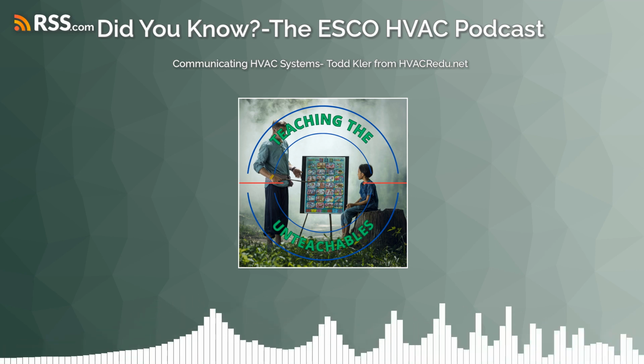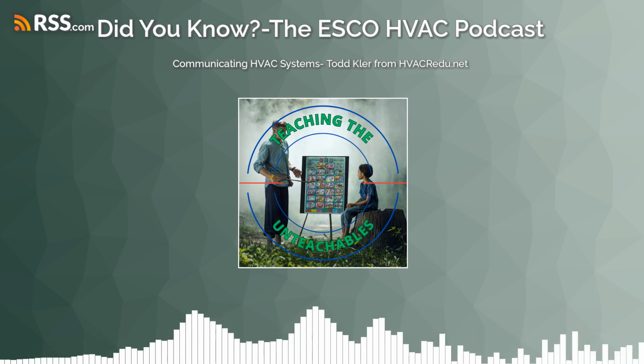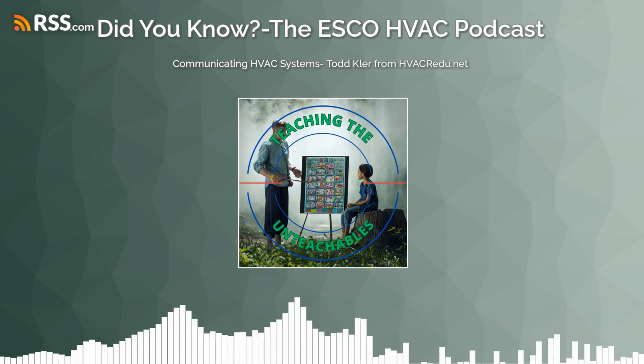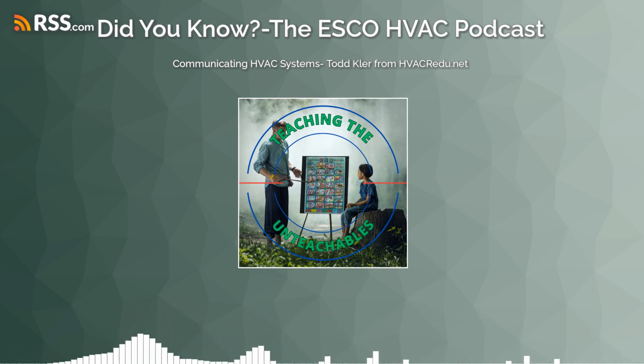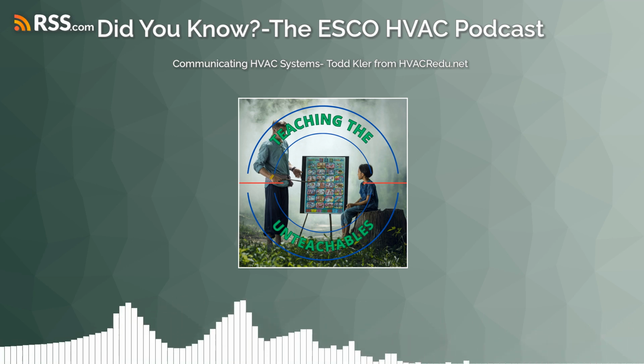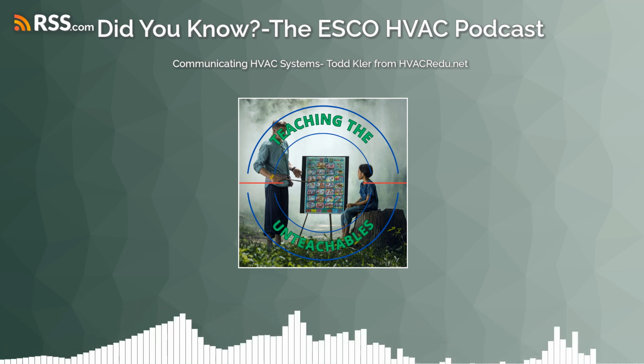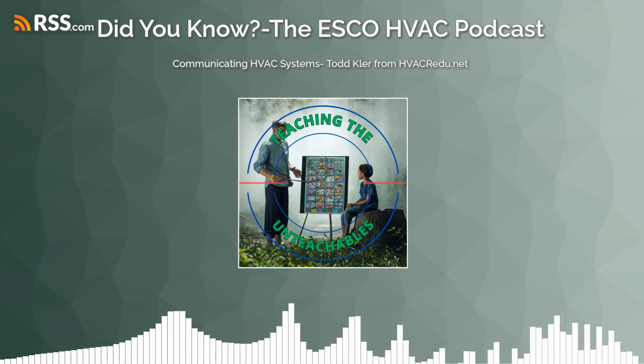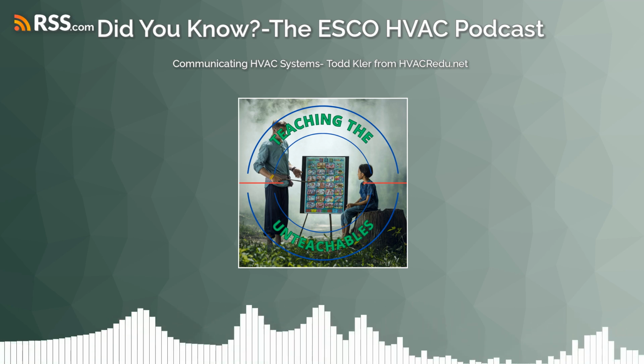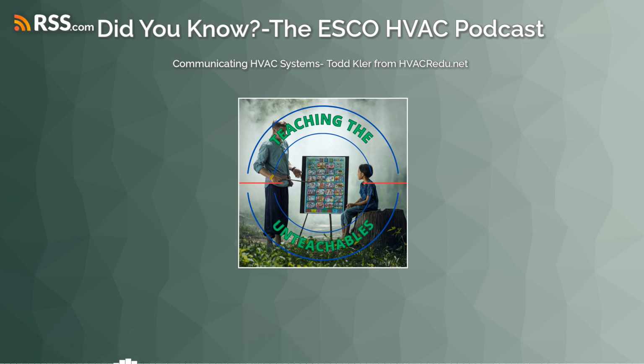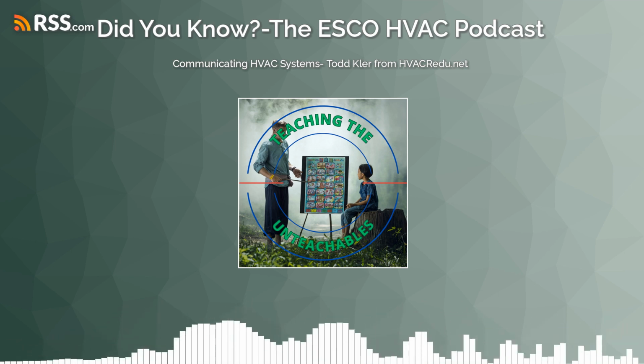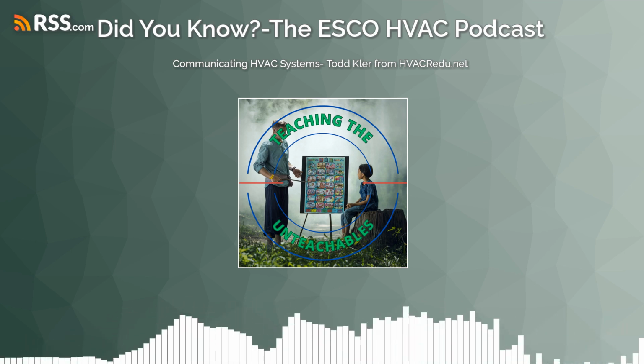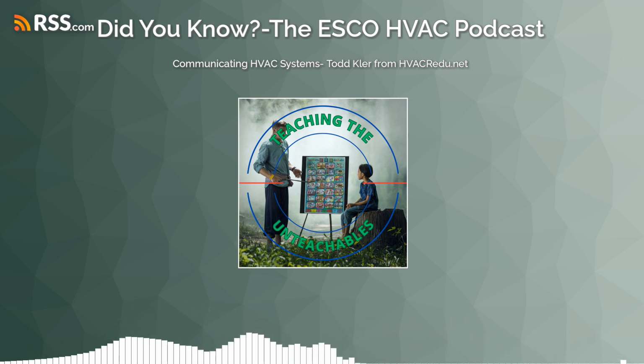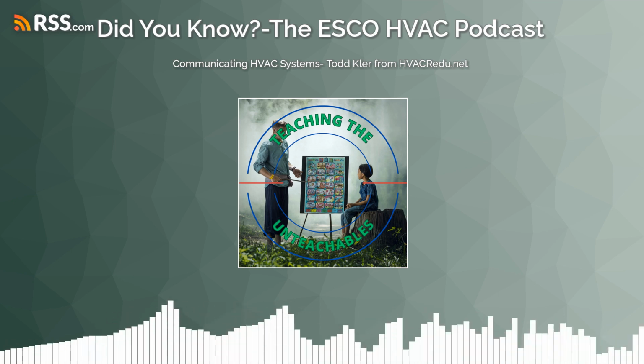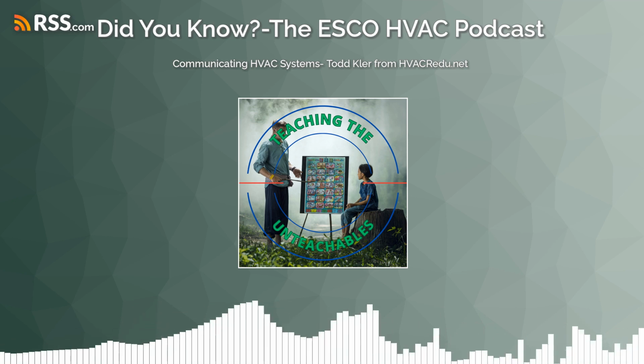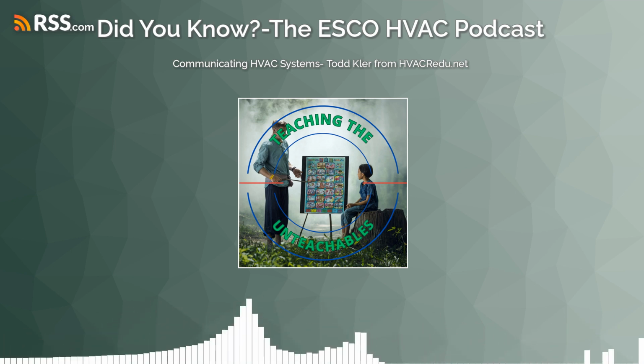Yeah, I see two primary connections because they've had a couple different generations of it, right? So you'll see one that is labeled ARCB, primarily using green, red, black, and blue or white wires. And then you can also see a variation of that is just common, B, and A. And I like finding this one in their service manuals. Remember, almost all this comes right out of the service manuals. This is not like hidden stuff. You have to read it to find it. But it's in there. You have to read, right?